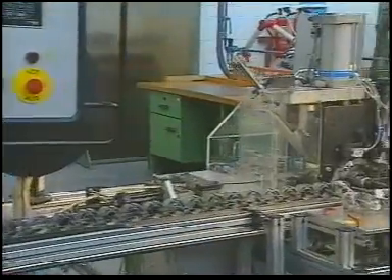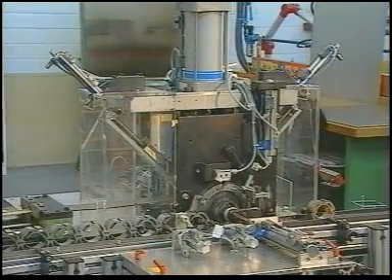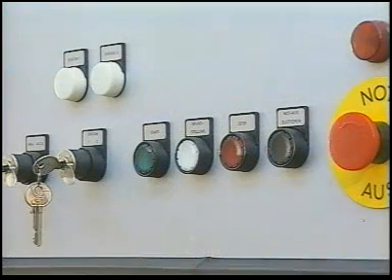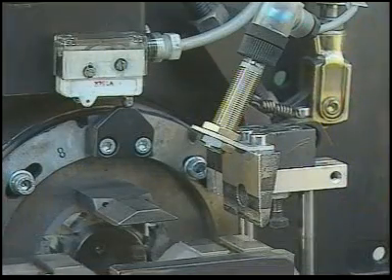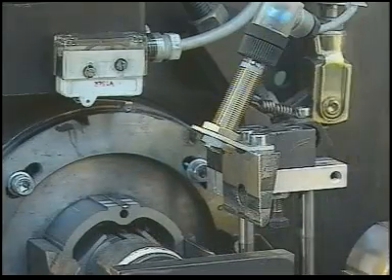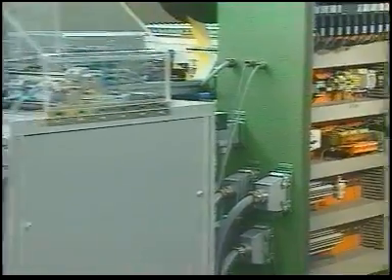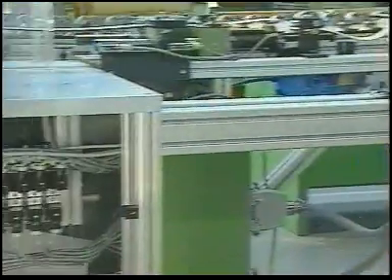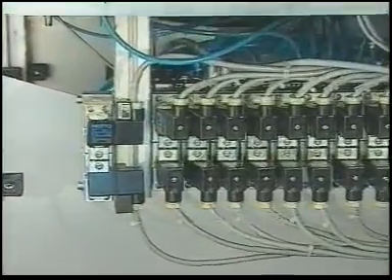Now let's take a look at what happens in practice. The elements of the control part are, of course, distributed throughout the entire system. The signal elements, here the push buttons for operation, the sensors, and the solenoid switches on the pneumatic cylinders send electrical signals to the machine controller. From there, the solenoid valves are controlled. So here we have the interface between the electrical signal part and the pneumatic control part.